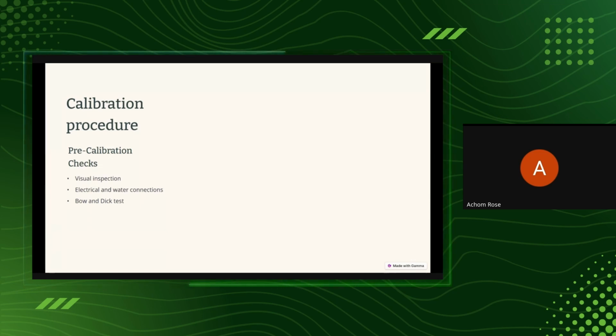First, we do the visual inspection. You want to see that the door is well, the gasket is okay, there are no leaks, the jacket is fine, and so on. The electrical and the water connections where applicable, you want to be sure that there's distilled water, so that you don't end or abort a procedure just because there is no water. Okay. And then it is also good to do a Bowie-Dick test because this helps us to know that the jacket is really able to maintain the right pressures in the chamber.